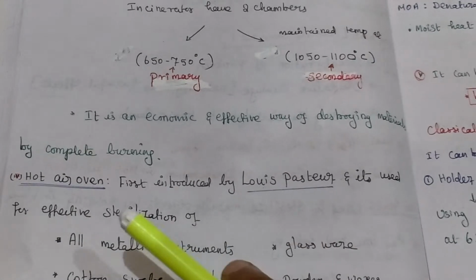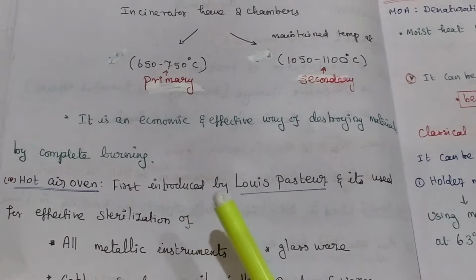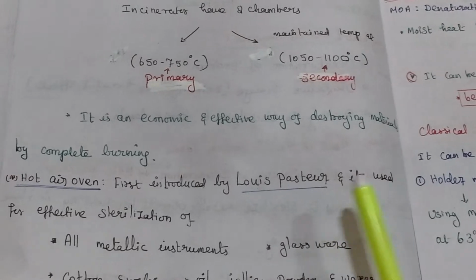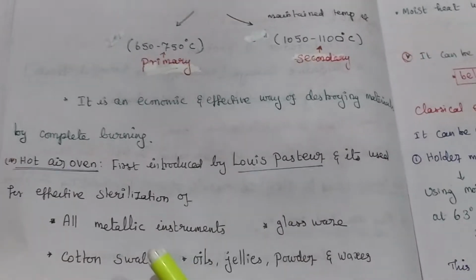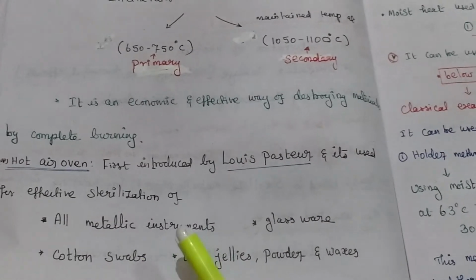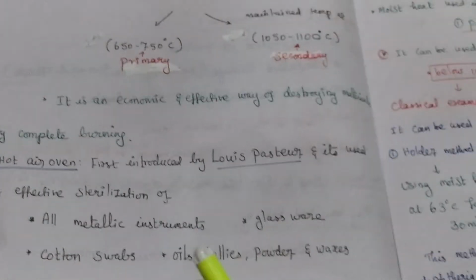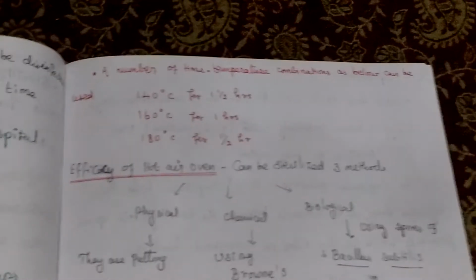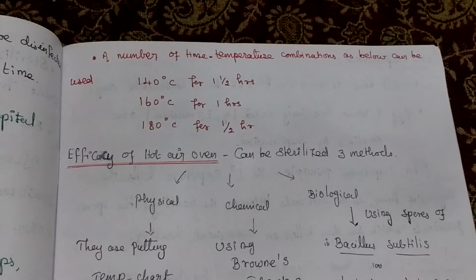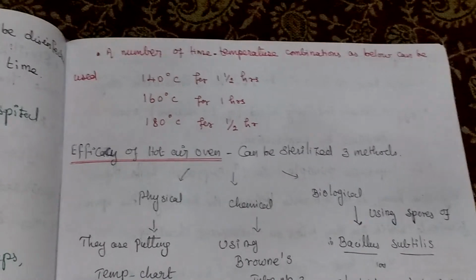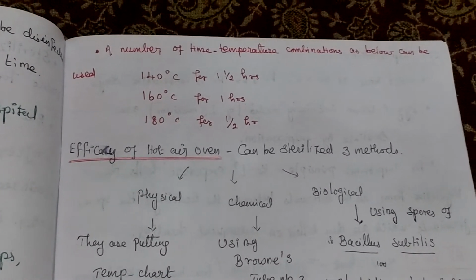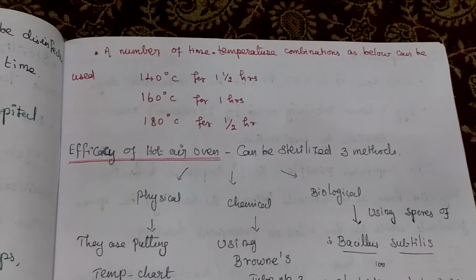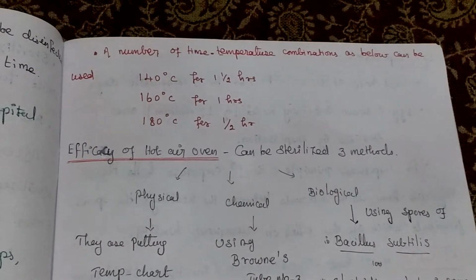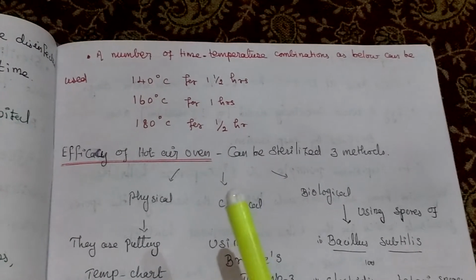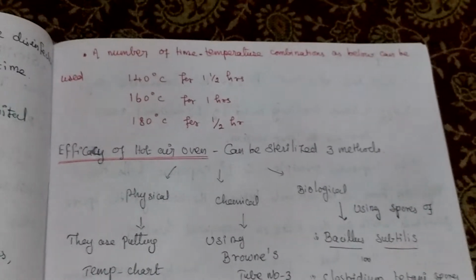Then the fourth one is the hot air oven. This method was first introduced by Louis Pasteur and it is used for effective sterilization of all metallic instruments, glassware, cotton swabs, oils, jellies, powders and waxes. Then a number of time-temperature combinations as below can be used. 140 degrees Celsius for 1.5 hours, or 160 degrees Celsius for 1 hour, or 180 degrees Celsius for half an hour. These time-temperature combinations only we will give for the hot air oven.